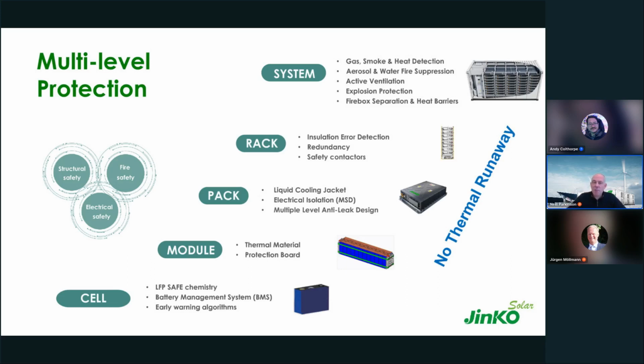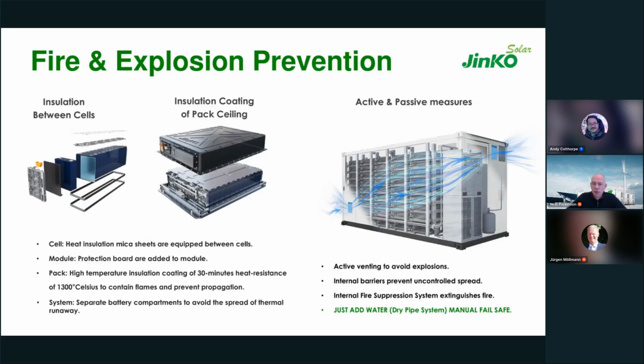Inside the pack itself, we have intumescent material coating the inside of the pack, which means that you have 1300 degrees protection for a period of time. We can have that up to 1 hour. Typically, it's 30 minutes at the pack level, and at the container level, we've got 1 hour of fire protection. So in terms of the fire and explosion proof, the deflagration that we talked about earlier, the insulation begins at the cell level. So we protect against heat transfer between cells to mitigate against thermal runaway within the pack itself. We use very commonly used technology, mica sheets, very high temperature sheets.